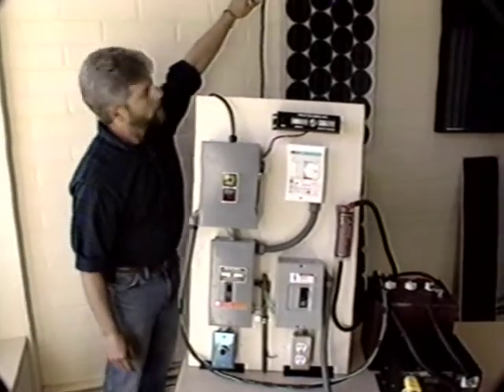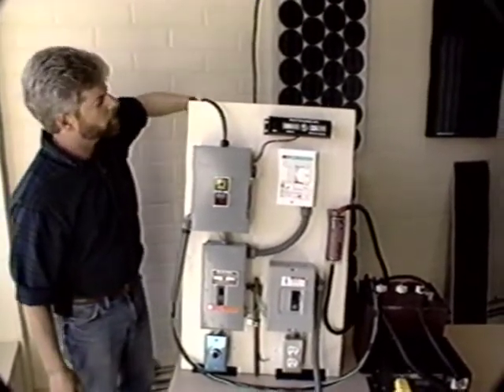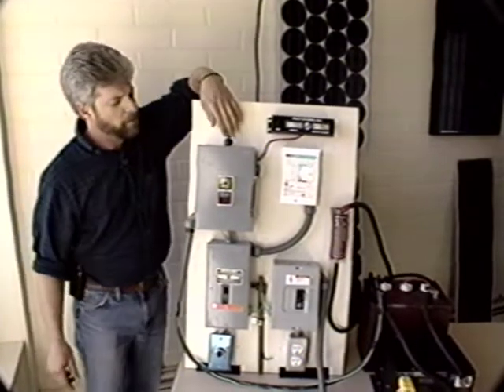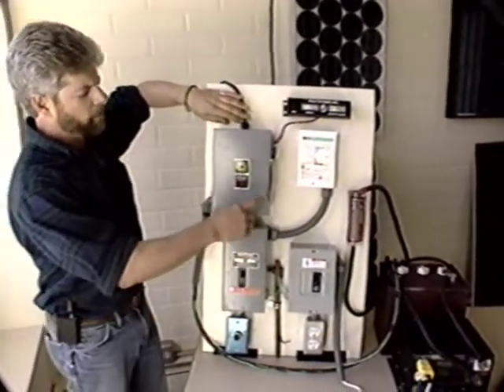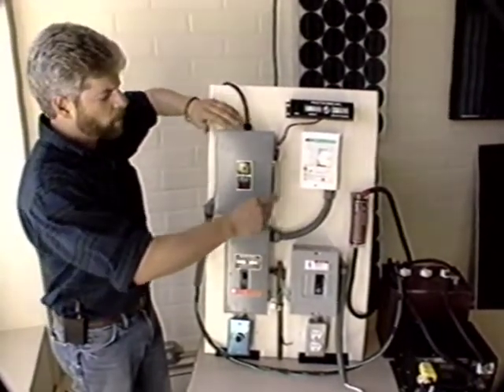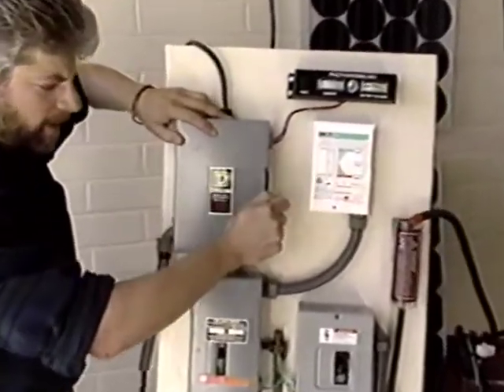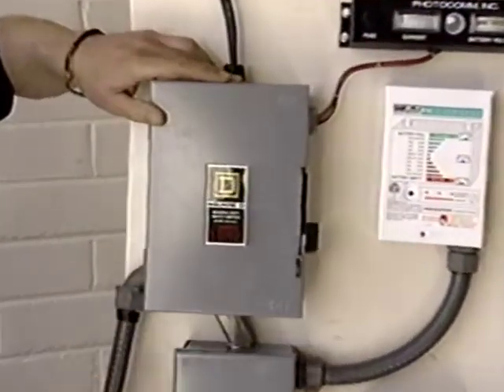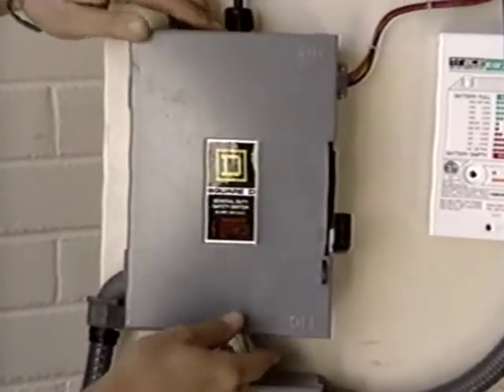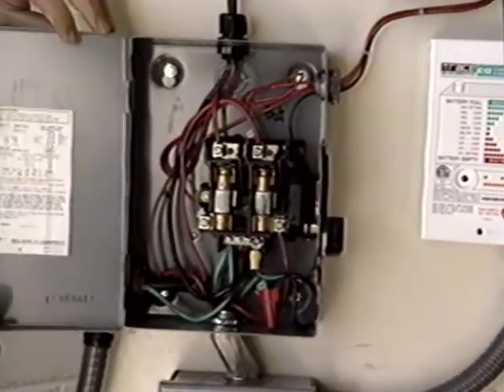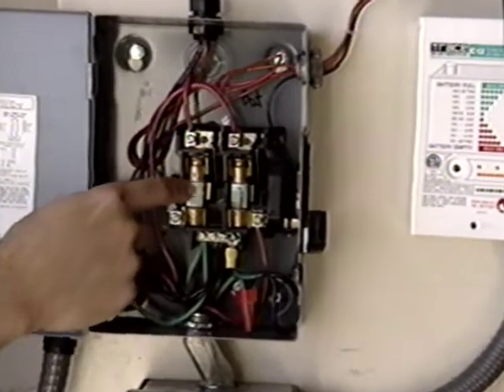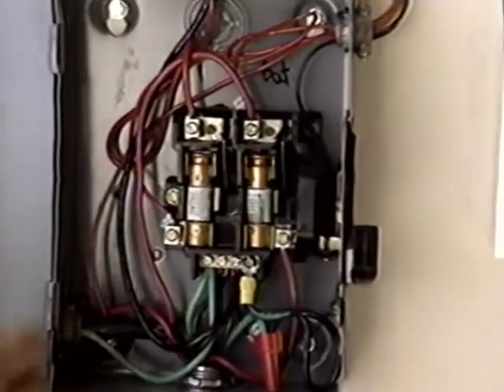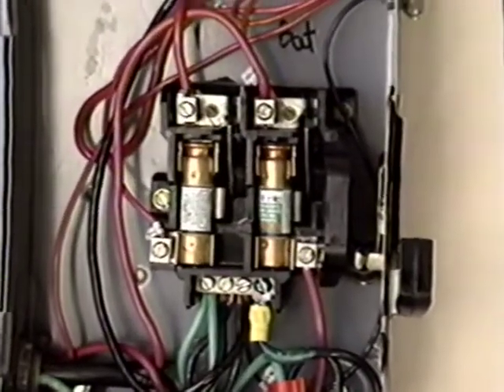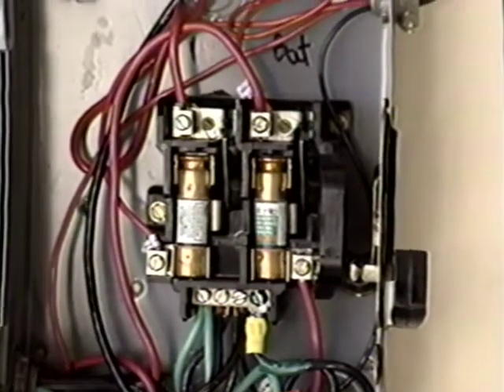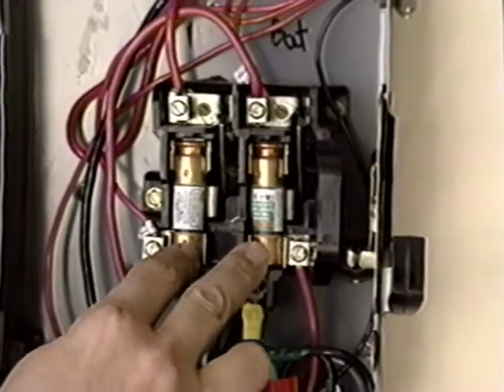The energy coming in here from the sun through this cord here comes first into what we call a fused disconnect. We've got a way to disconnect this source of voltage from the rest of the electrical equipment so we don't get a shock. Inside here, we've got fuses, and fuses are required by code to protect the wires from overcurrent. It's overcurrent protection. So in this case, we've got what's called a single throw, double pole fused disconnect.